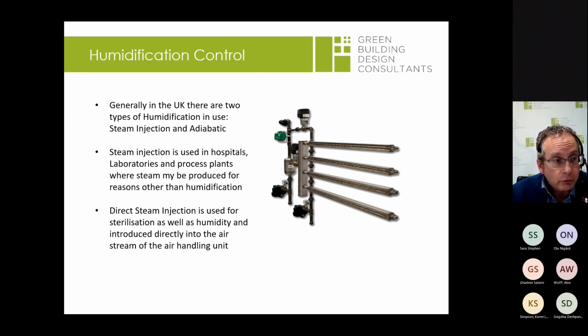So the steam injection, there's a picture there. If you can imagine, steam gets generated in the pipework, and then through various pressure vessels on the left-hand side, it gets emitted down into those stainless steel tubes, and then a very small amount of steam gets injected into the air ducts inside the AHUs, and obviously that's where the steam is then added to the system.